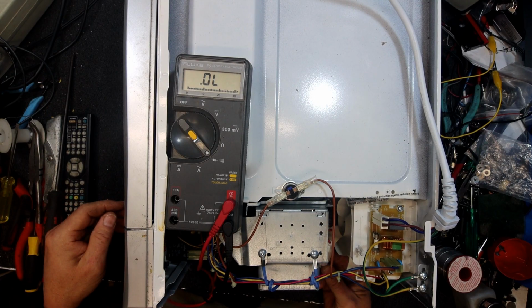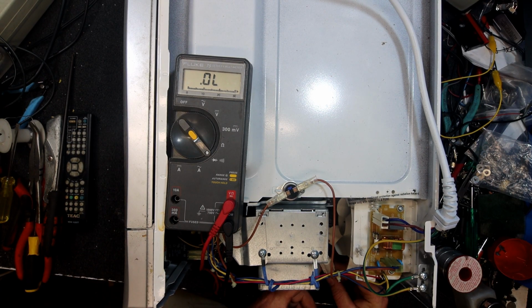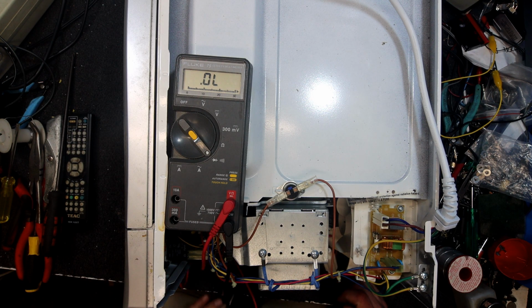We've got this big high voltage fuse here, a bit hard to see, but it's just a big plastic tube. It's got 5 kV, 0.7 amp written on it - that's its rating, so they do come in different amperage ratings. It goes between the capacitor and the transformer terminal, and it should measure short. If that's open circuit, normally something in the high voltage side is blown. You always have to remember to check that when you're quoting the customer, because they used to cost about $8 or so. Make sure you check the fuse isn't blown.